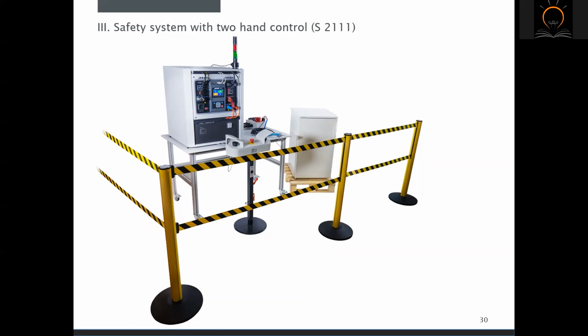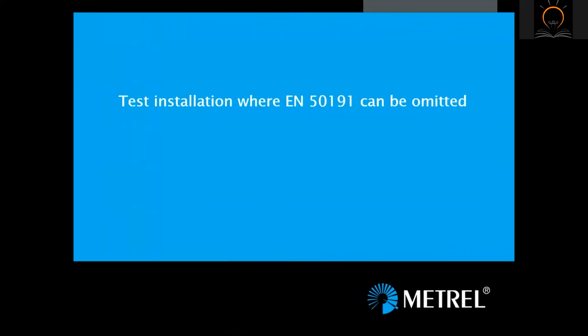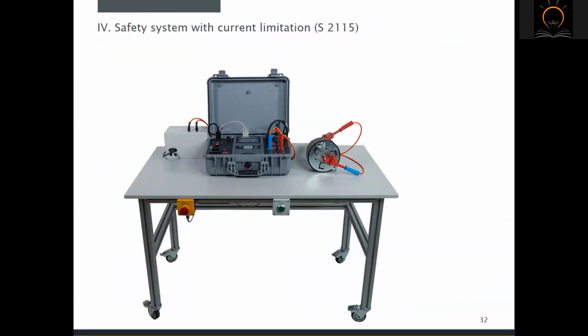The main job of the two-hand safety device at this type of safety station is to prevent the user from performing hazardous tests when exposed to the risk of electric shock. Test installation where EN 50191 can be omitted. Ensuring safety at work is a requirement of the Association for Employers' Liability Insurance. Safety requirements for execution of high voltage tests are defined in the standard EN 50191.